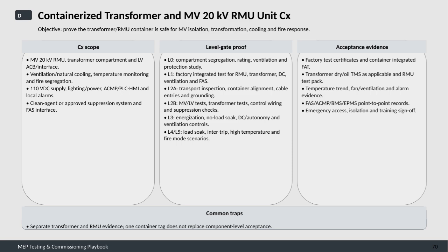Level 3 focuses on energization and no-load soak tests, DC autonomy, and ventilation controls. Finally, Levels 4 and 5 cover load soak tests, inter-trip functionalities, high temperature, and fire mode scenarios. The acceptance evidence required includes factory test certificates and the container's factory acceptance test.